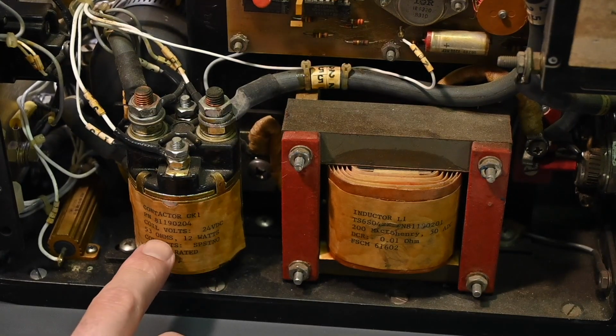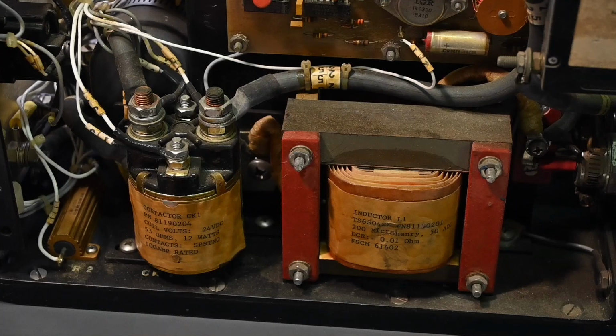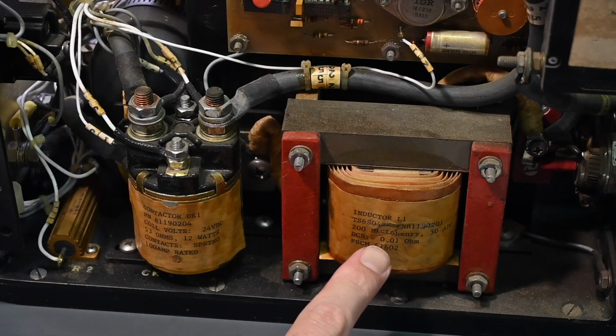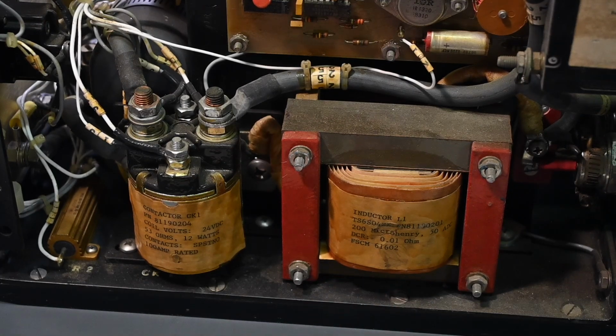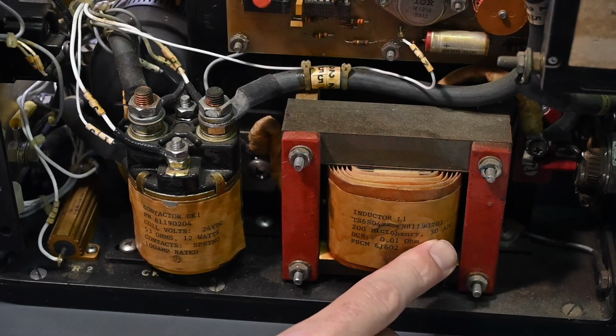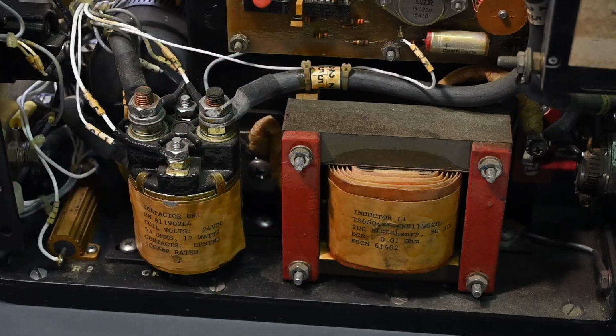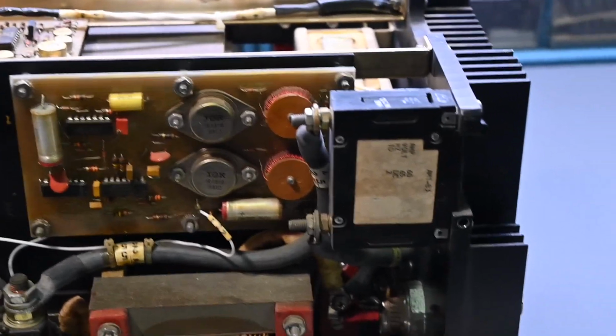So this says contactor, there's a part number, coil voltage 24 volts, 53 ohms, 12 watt. Contacts are rated 100 amps. So we know that the current draw is going to be 100 amps or less. Now there's an inductor right here, and it says 200 microhenry and looks like 50 amps. DC resistance 0.01 ohm. So this is a 50 amp. They've definitely overrated this, and 50 amps is probably about going to be the limit of what this is going to require.